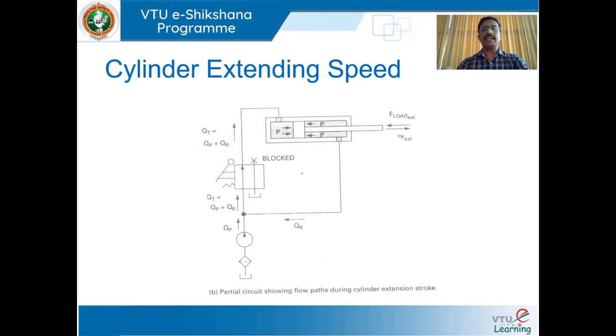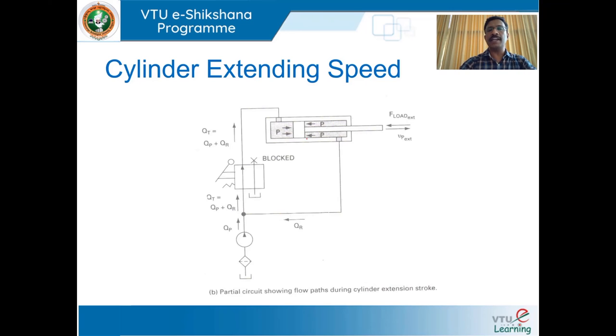We shall discuss the cylinder extending speed. A partial circuit shows flow paths during the cylinder extension stroke. The rod side oil is regenerated and, along with the pump flow, the regenerated oil enters into the blank end of the cylinder and cylinder extension takes place. The regenerative circuit is used to increase the extending speed of the cylinder — the extending speed will be greater than the normal double-acting cylinder.